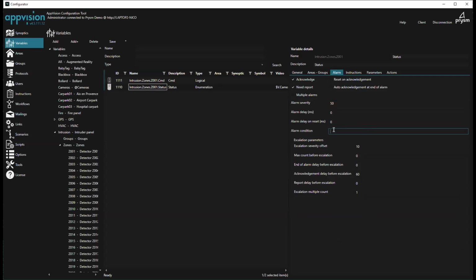So you can use this, it's easy. And also here you can, by default, do a link to a timetable. So you can say, I will do an alarm only if my timetable T14, sorry, equals 1. This is another type of condition, and you can have multiple conditions, AND, OR, etc. So it's a shortcut to avoid creating links for that.